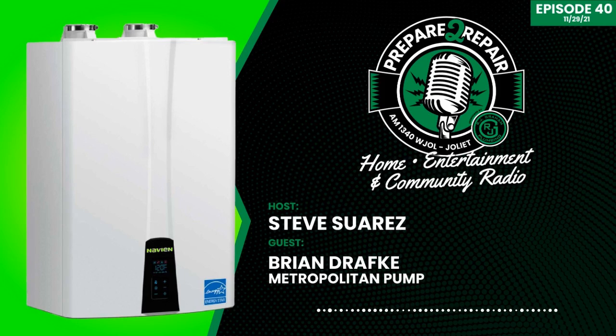Could be a year or two before your power ever goes out, so what we're doing is exercising that second pump. It's always good to do it. If you let your car sit in the driveway for a year and go to start it, is it going to start? Nine times out of ten, no. That's basically the way a battery backup is - it sits there doing nothing until it needs to be done, until a failure on your main. So with an alternator, we have our backup pump running one time, then our main pump, back and forth, back and forth. So we exercise the pumps.